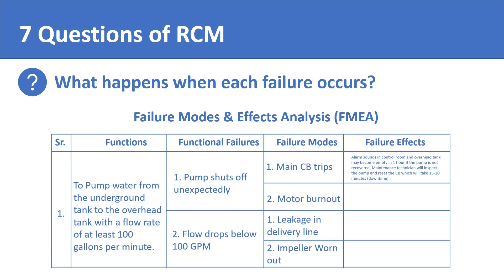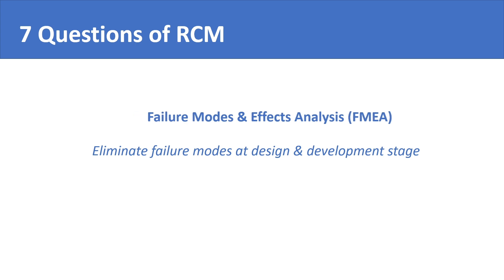An interesting point is that RCM can be applied at the design and development stages of projects in order to eliminate failure modes. Under such a case, the failure modes and effects analysis is referred to as design FMEA. In design FMEA, reliability and maintainability is baked into the project.